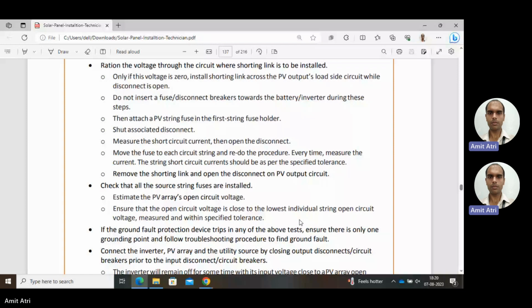The string short circuit current should be as per the specified tolerance. It means voltage and the current, open circuit voltage, then short circuit current, they should be within the specified range. They should not be more or below the specified level. They should be up to a required level or the standard. Next, remove the shorting link and open the disconnect on the PV output circuit. After that, check that all the source string fuses are installed. Okay, fuses in the string, the source string.